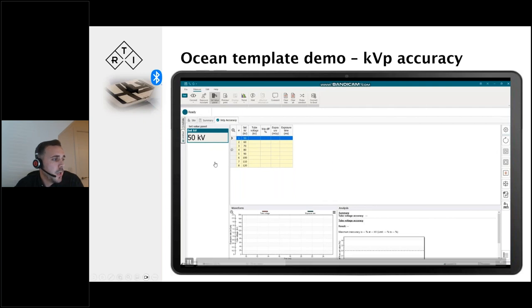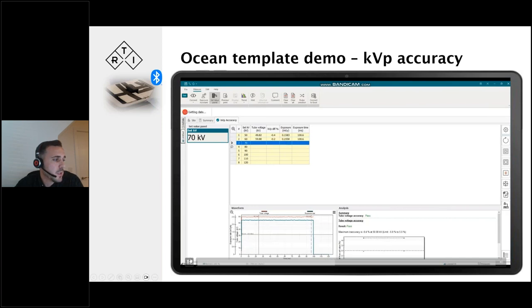I'm gonna click OK. As you see, this is a very simple template, but all I need to do is see the value on the left-hand side, 60 KV, make an exposure, and everything is done automatically. This one's 70 KV. And as you can see, I've got a hint coming up, which means I've customized it with another image, which you can do throughout the workflow as well.